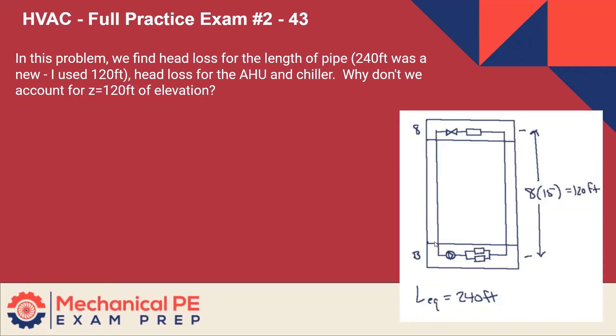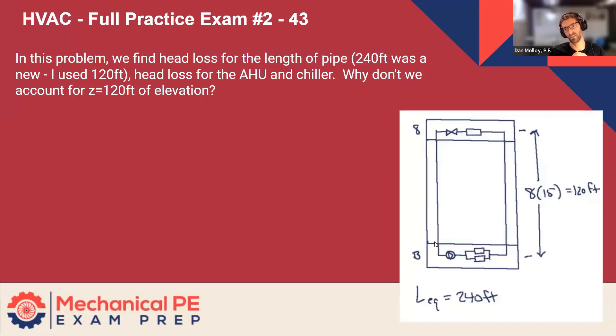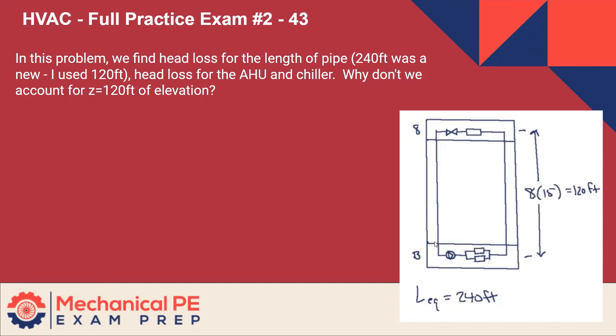I think I had a similar problem to this — if you're calculating the head loss across the AHU and chiller on the same elevation, on the height of the building, then the differential wouldn't account for the height of the building, right? Well, the chiller is in the basement and the air handler's on the eighth floor. Does that change anything? No, because you're accounting for the pressure drop between the AHU and the chiller.